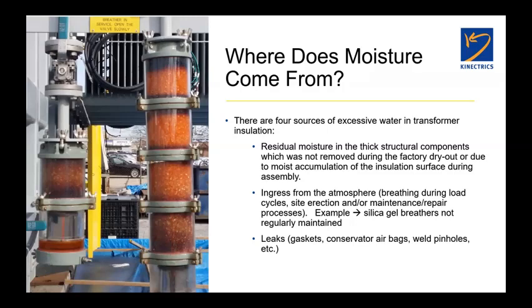I've seen several transformers over the years I've been in the business where we have porosity in welds, and they allow oil to come out. And I always mention to folks, if you see weeping oil or evidence of oil seepage anywhere on a transformer, and typically if there is any, you'll see the dirt that accumulates on a transformer tank will have that wet look. Any leak in a transformer under the right circumstances can be a two-way street for atmospheric moisture to get inside the unit. So you want to treat leaks extremely seriously.